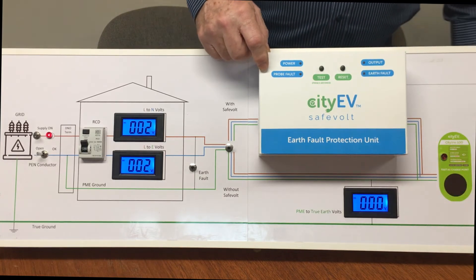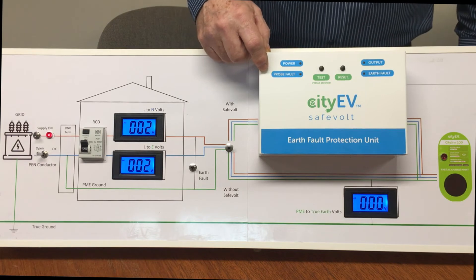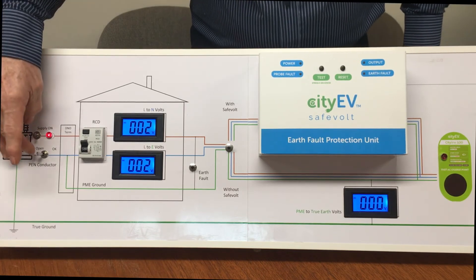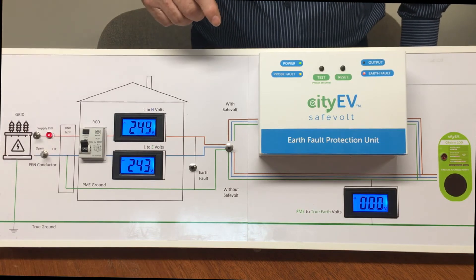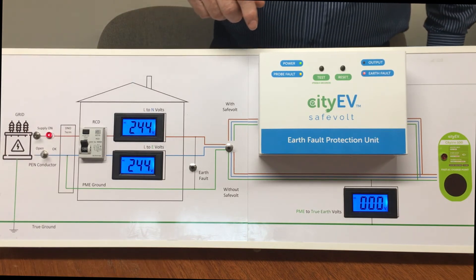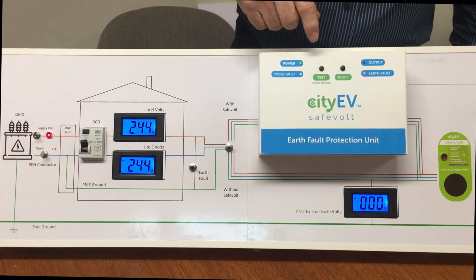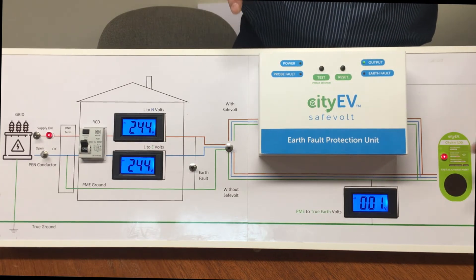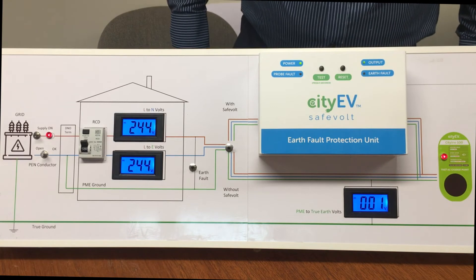The vehicle plugged into the charge point is now completely safe. When we reconnect the PEN conductor, voltage returns to normal, the Safevolt resets, and everything is restored to normal operation.